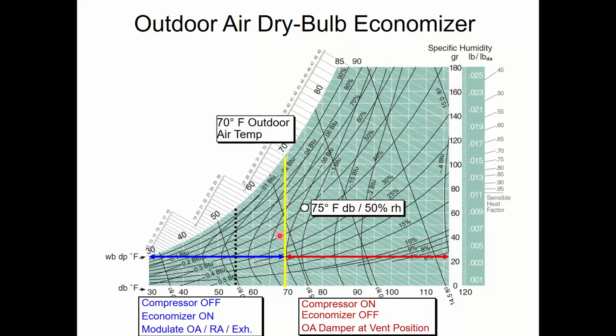So the percent means how close to saturated am I? 50% means I am halfway to being saturated. But 50% means something different on a cold day versus a hot day. So if someone asks you how humid it is, 50% is useful in terms of how well my body can sweat to the air. And that's a whole other discussion. That's another 3 or 4 hour webinar on the way your body rejects heat. So let me know if you want that, on how good I can sweat the water from my body to the air. But it doesn't really tell me how much moisture is in the air unless you tell me the temperature.